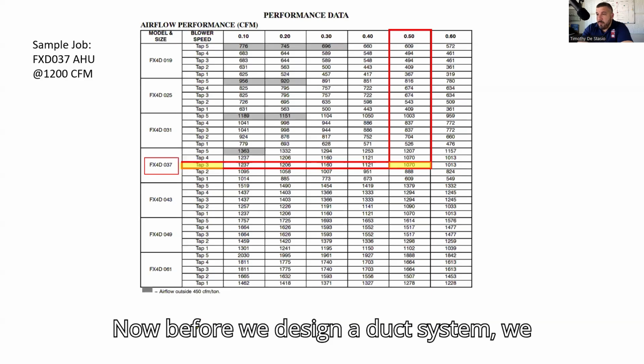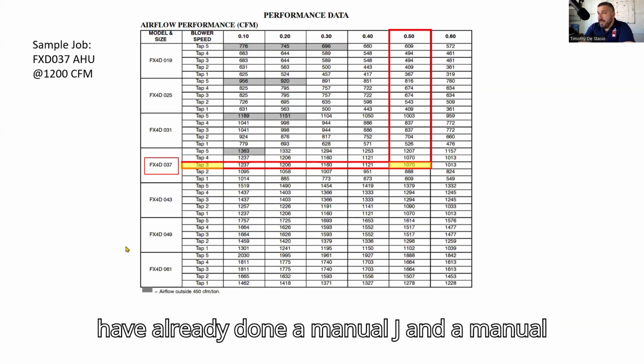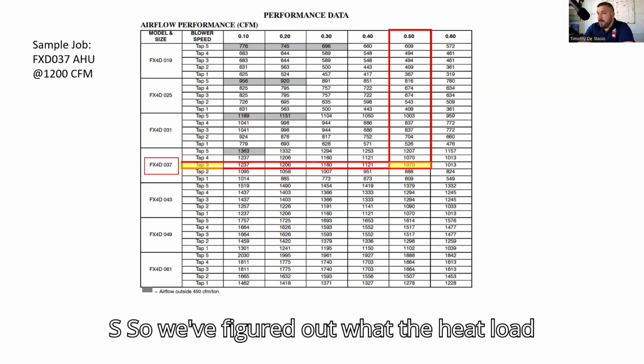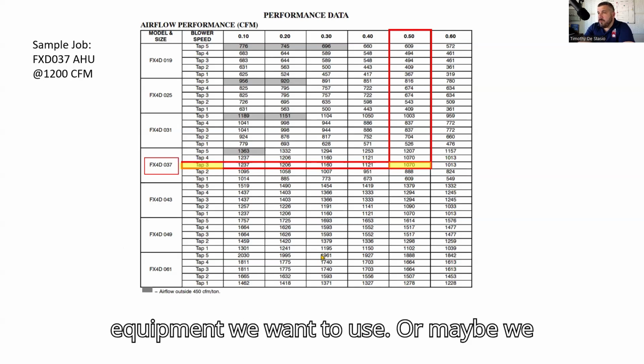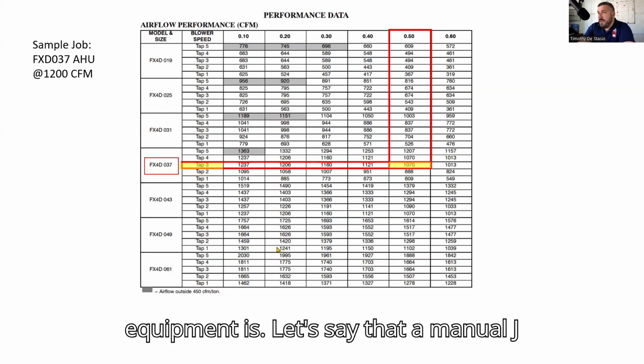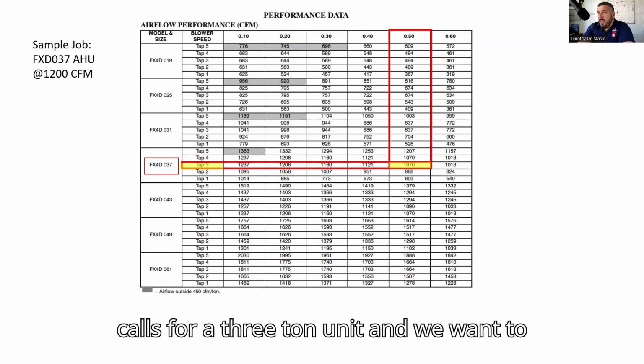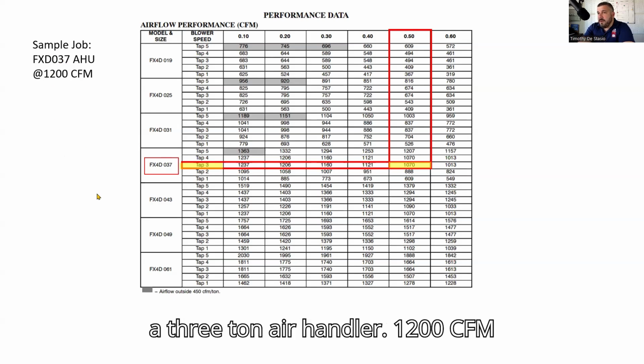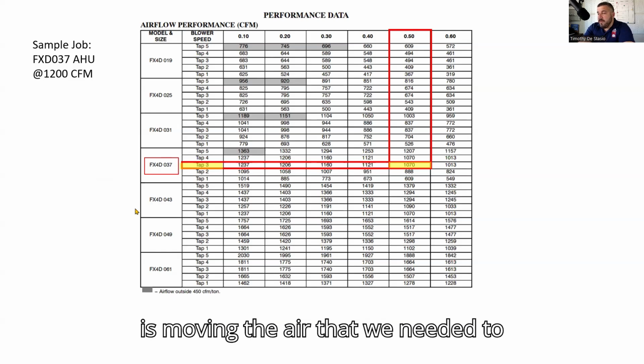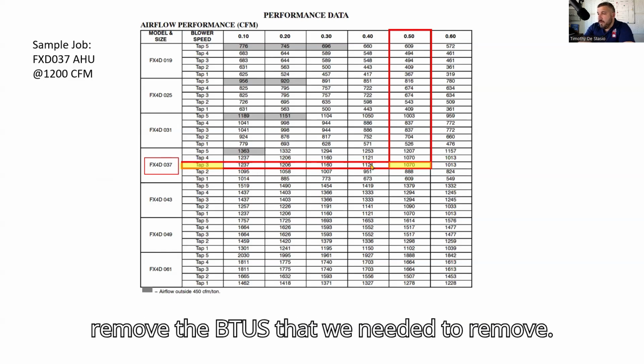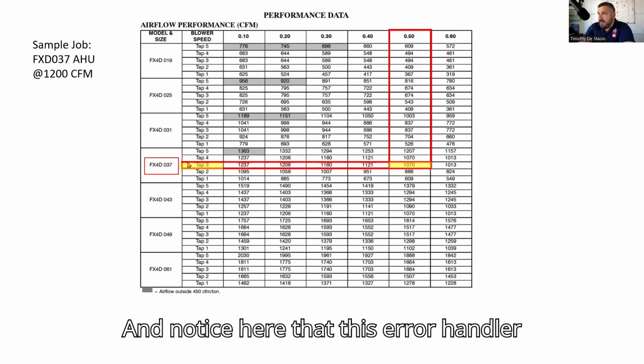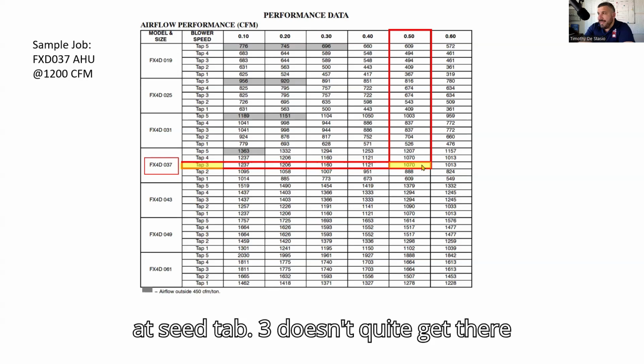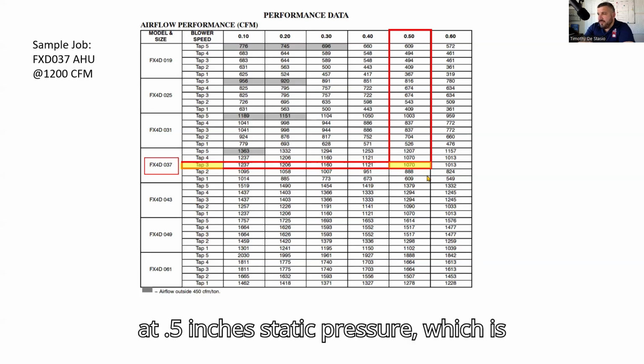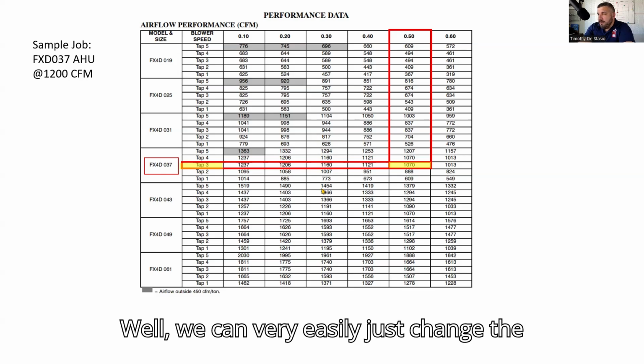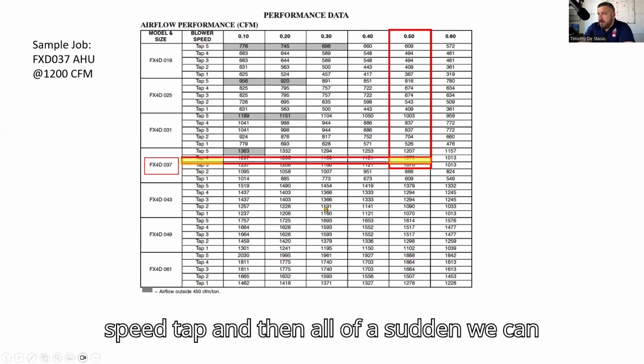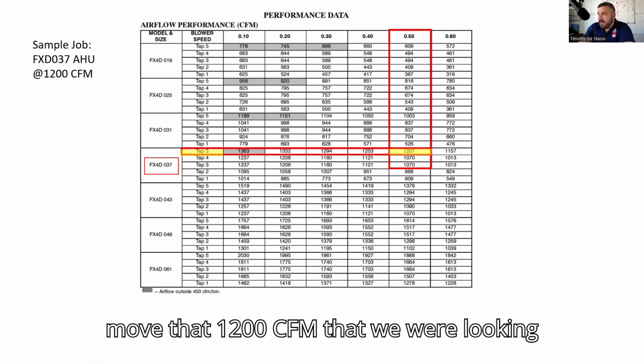Now, before we design a duct system, we have already done a Manual J and a Manual S. So we've figured out what the heat load is on the building and we figure out what equipment we want to use. Or maybe we almost have figured out what that equipment is. Let's say that our Manual J calls for a 3-ton unit and we want to pick this air handler right here. This is a 3-ton air handler. 1200 CFM is moving the air that we need it to remove the BTUs that we need it to remove. And notice here that this air handler at speed tap 3 doesn't quite get there at 0.5 inches static pressure, which is kind of our starting static pressure. Well, we can very easily just change the speed tap, and then all of a sudden we can move that 1200 CFM that we were looking for.